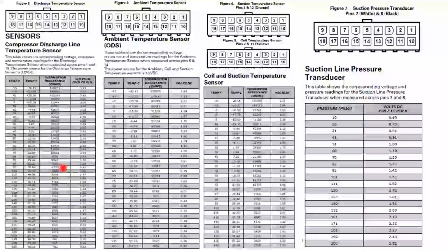So we're going to go off of our pressure temperature charts right here. Disconnect power. Ambient temperature, number 5 and 14, black wires. If we disconnect power and it is 70 degrees out, and we're taking the readings across pins 5 and 14 with nothing attached, it's going to register 11,717 ohms.